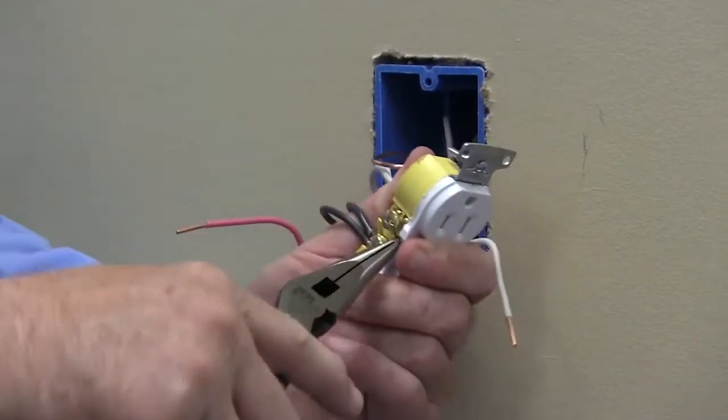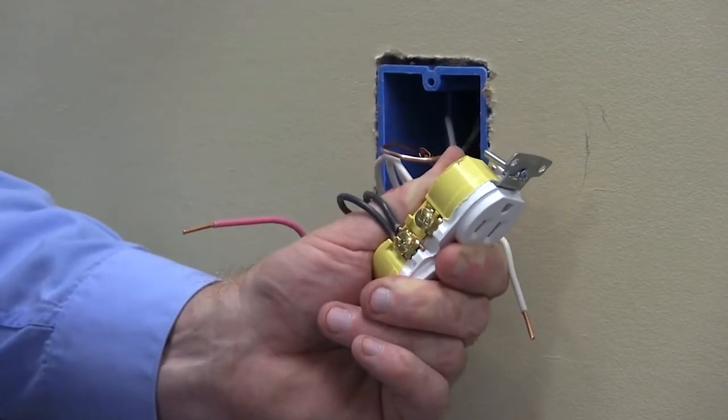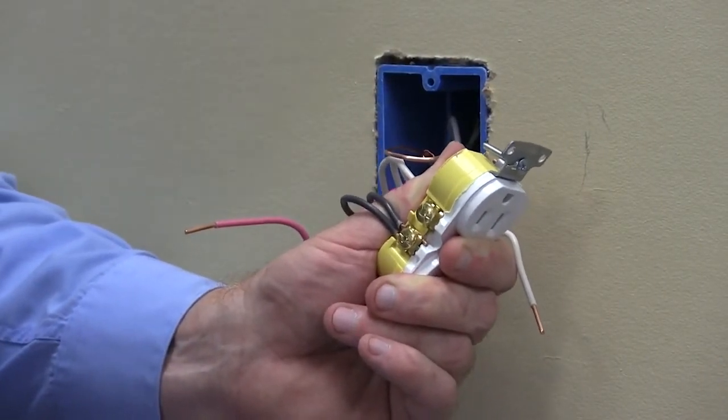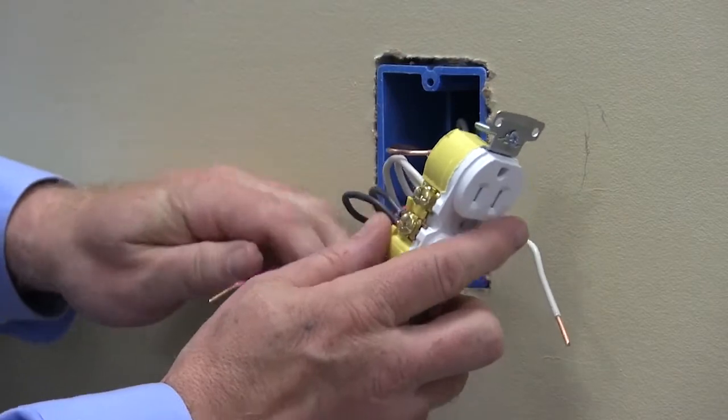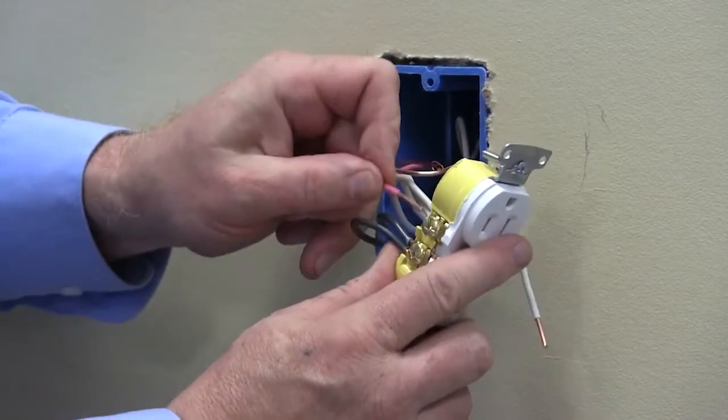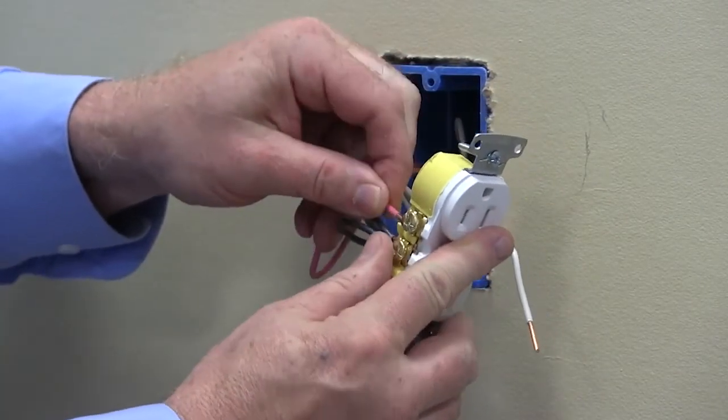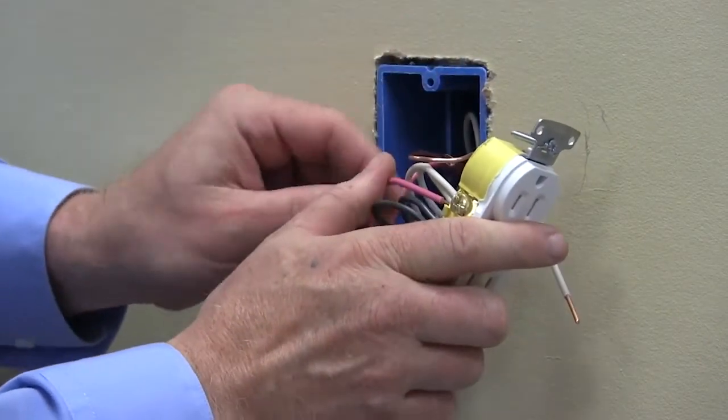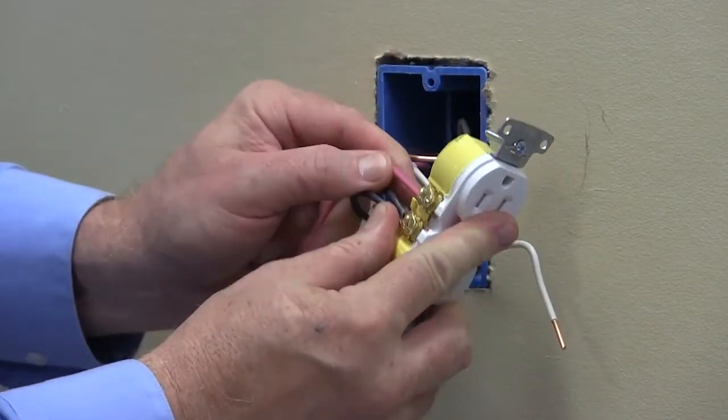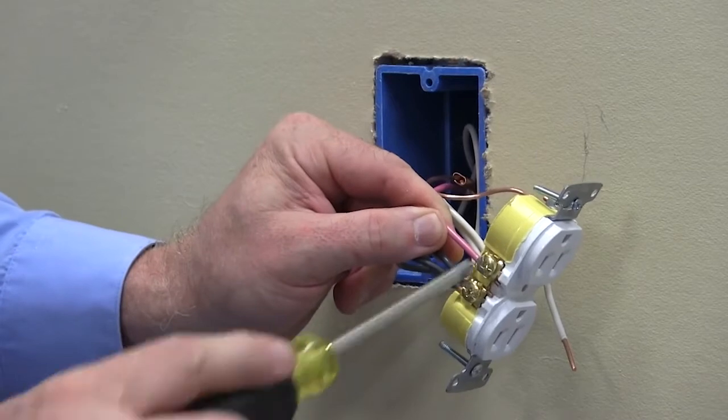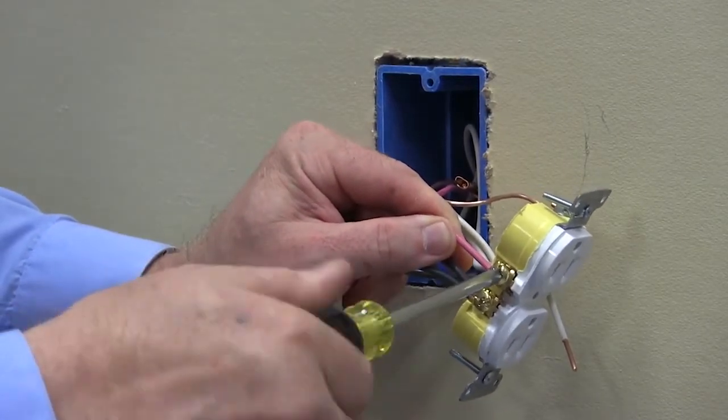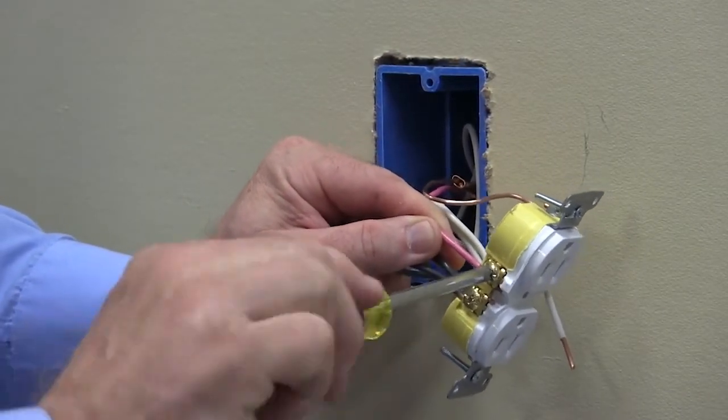Now, we would like to show how to split wire this receptacle. Break off the break off tabs as you would typically do for split wire. We have already terminated the bottom half of the receptacle with the power in and downstream feed through. Using the red wire, terminate the top half of the receptacle for split wire circuit control.